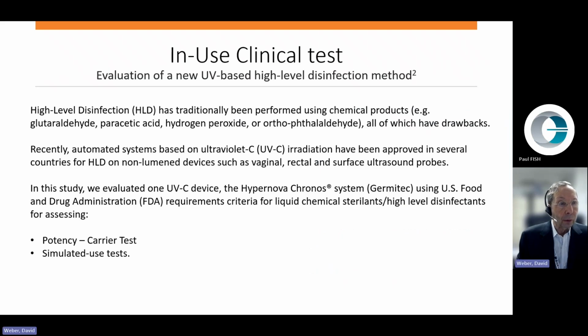Well, let's now talk about evaluation of a new UVC-based high-level disinfection method. HLD has traditionally been performed using chemical products such as glutaraldehyde, peracetic acid, hydrogen peroxide, or orthophthalaldehyde, all of which have drawbacks. Recently, automated systems based on UVC irradiation have been approved in several countries for HLD on non-lumen devices such as vaginal, rectal, and surface ultrasound probes. In this study, we evaluated one UVC device, the Hypernova Chronos system, Germitec, using U.S. Food and Drug Administration, FDA, requirements criteria for liquid chemical sterilants, which are also high-level disinfectants, for assessing potency carrier tests and simulated use tests.